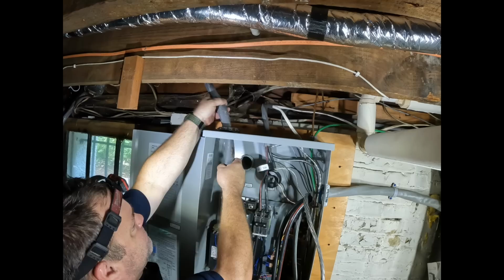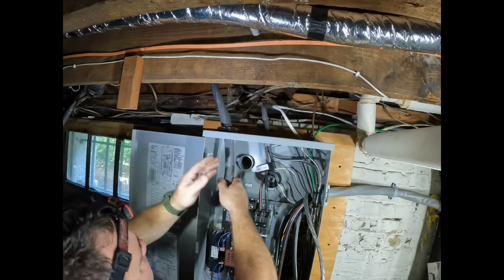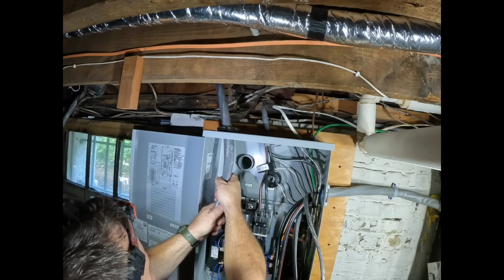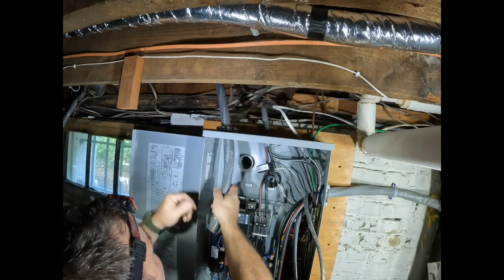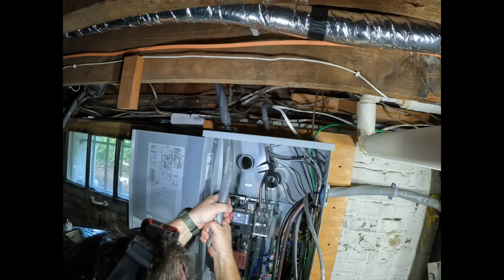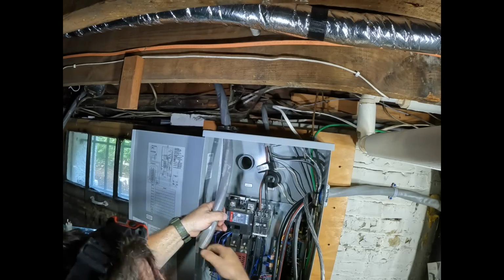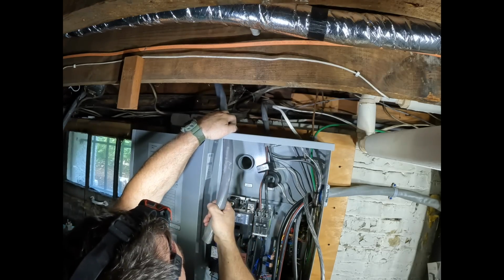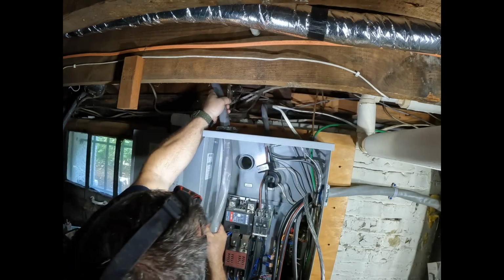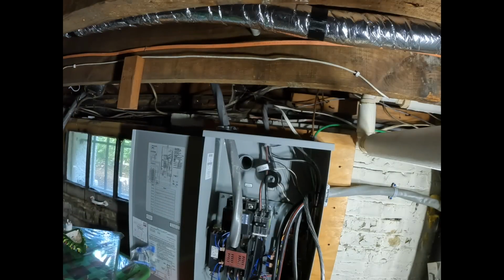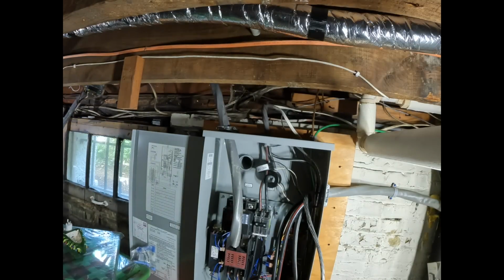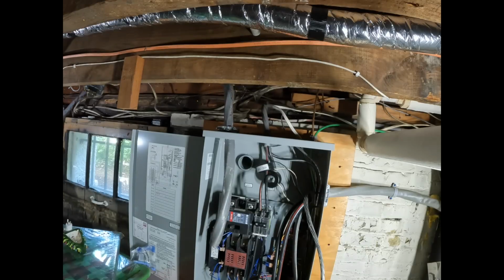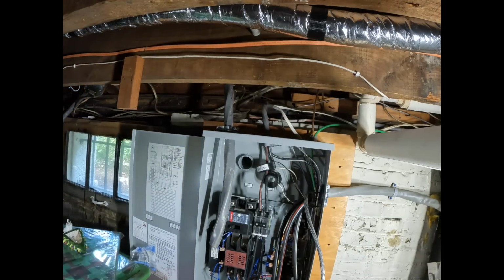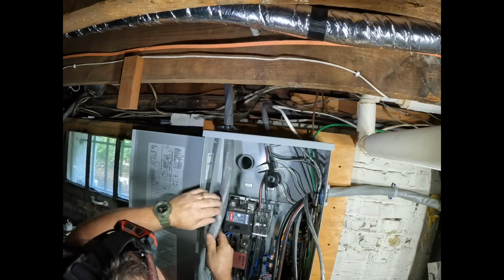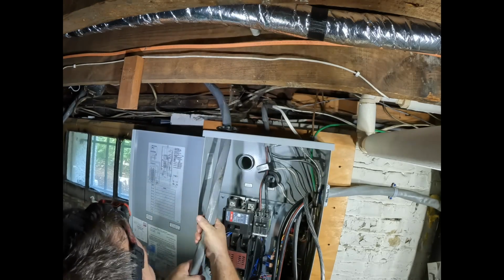I'm not too concerned about damaging the insulation here because it's going to be inside the enclosure. When you pull a wire like this, you want to pull a little extra - a mile too long, but not two miles, is better than an inch too short. This was cut off the reel at 75 feet, and I just made it on the meter disconnect side and just made it at the transfer switch. It worked out perfect.